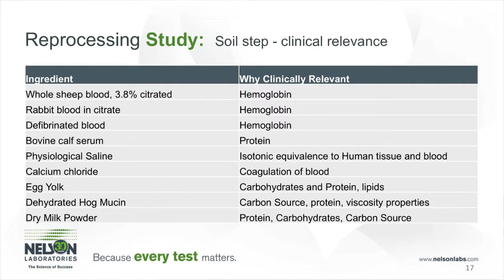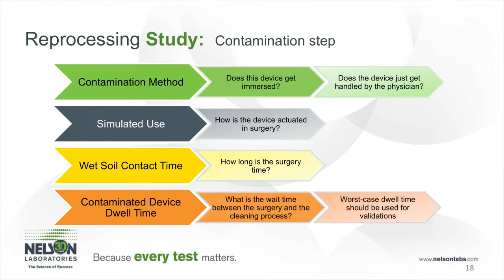The next step is the contamination step. We need to ensure that we are doing a simulated use worst case contamination. So we are performing a contamination exactly how the device would be utilized in a surgical setting. So we need to determine if the device is going to be, for example, immersed into the chest cavity, if it gets handled by a physician's bloody gloves, etc., and determining the exact test soil to be utilized.